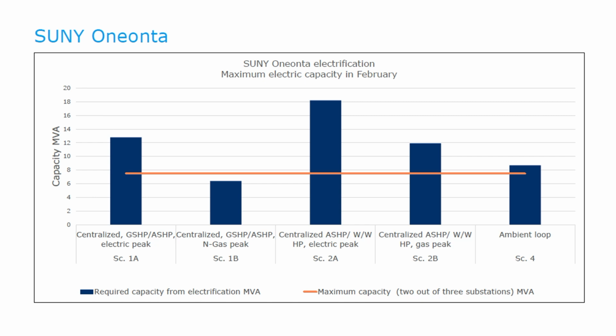You can see from these graphs, if we go for a centralized ground source heat pump or air source heat pump, the electric peak's significantly higher. We're looking at electric peaks in the 18 megawatt range, 12 megawatts, which is more electrical energy than our underground distribution network on campus can handle, and more than our utility can supply us. If you look at scenarios like natural gas peak, that's a 6 megawatt peak in February versus our 5 or 6 megawatt peak in September, which we currently have.